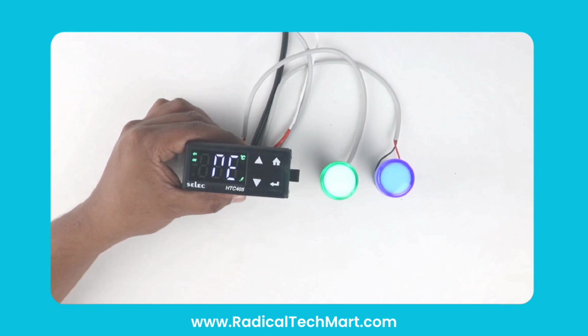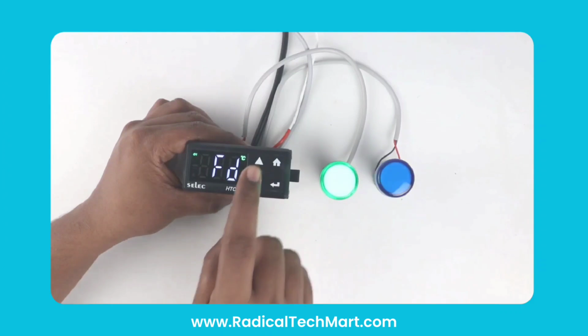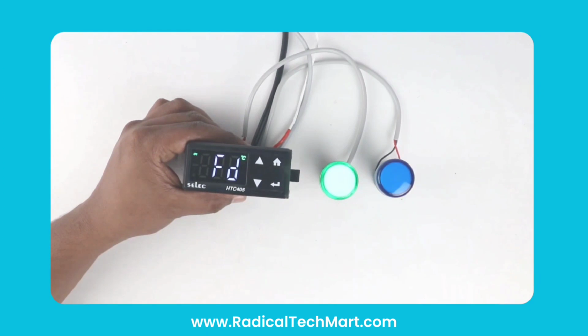Next is temperature control action. The default is RE, meaning reverse action. In reverse action, the relay stays on below the set point and turns off above it. Forward action means the relay stays on above the set point and off below it. I will keep it at reverse action and save.